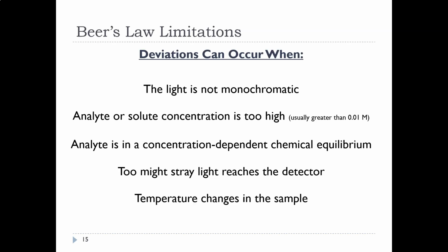It also doesn't work well if your reaction is at chemical equilibrium, especially if that chemical equilibrium is not product favored. And then if we have issues like the light, not only is the light not one wavelength, but if it's varying and open to where the light bulb in the room is being impacted, you can see that. So if we have stray light, the only light that the instrument is measuring needs to be coming from inside the instrument. If there's a window open, that's bad.